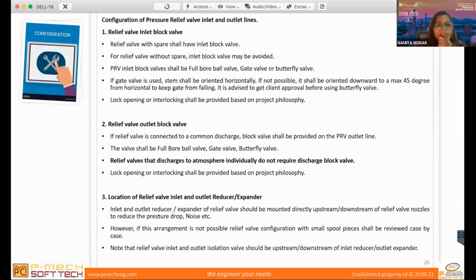Okay, so relief valve configuration, if you see, this is the relief valve, so inlet and outlet. You will have a block valve on both sides. You will have a drain at the upstream and a vent at the downstream. Then you will have the spool piece here at the flange, and a reducer on the upstream and an expander on the downstream of the PSV. So that's a typical configuration of the PSV.